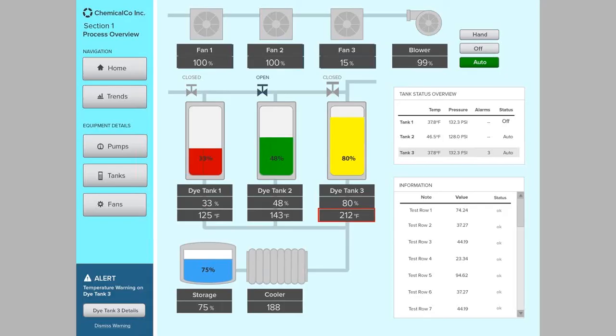So back to our example HMI, we've used proximity to split the navigation into 2 separate groups, navigation and equipment details. And we've brought the equipment labels down with the readouts to make a stronger connection between those bits of information. We've also resized the equipment graphics a bit too, downplaying their importance and giving the entire layout just more whitespace or breathing room.